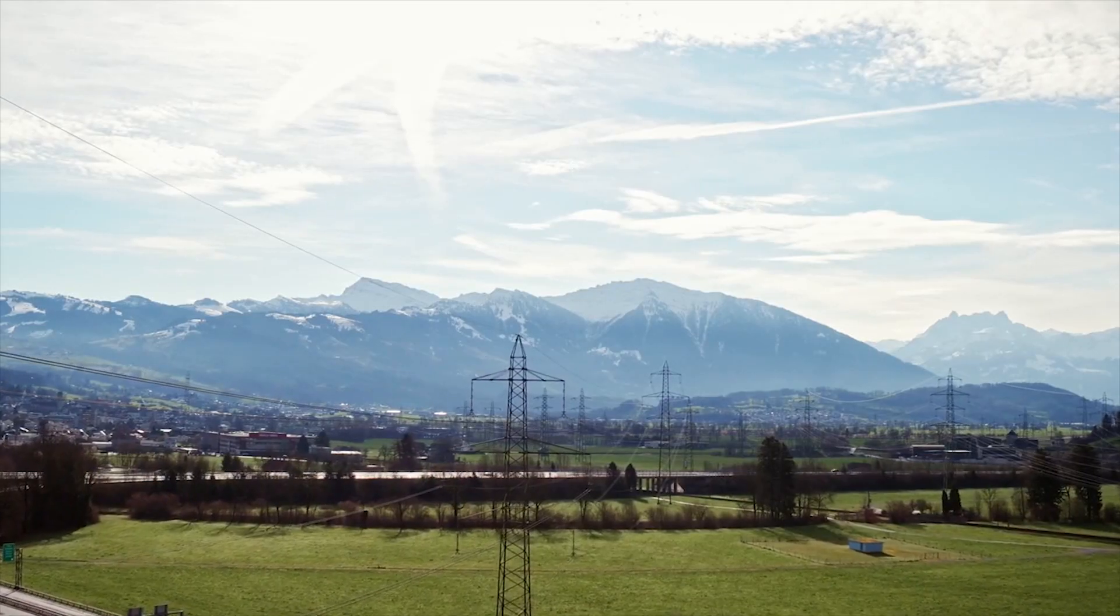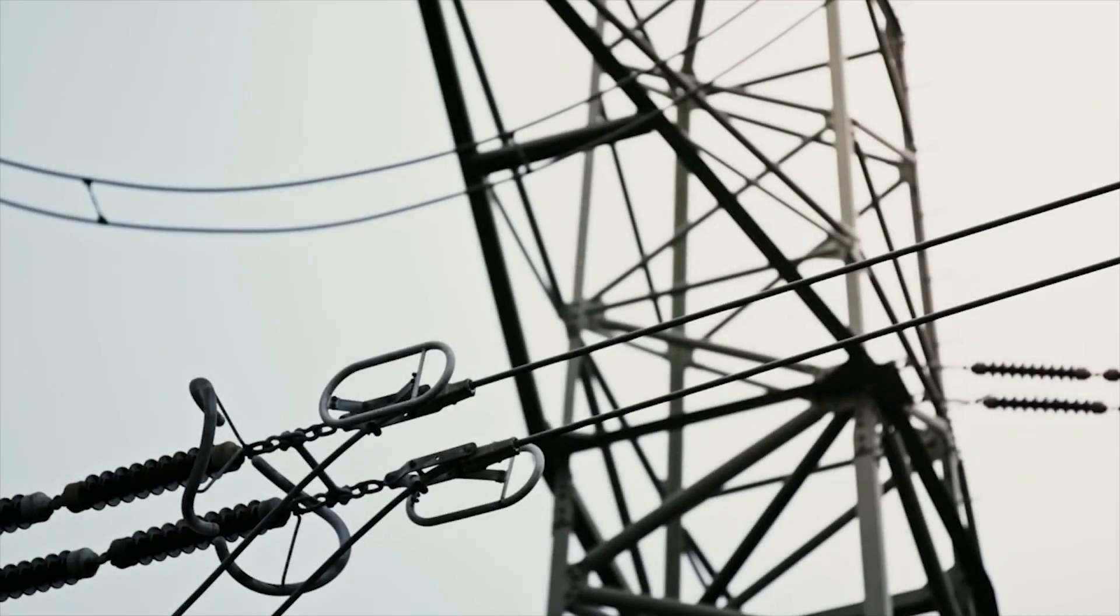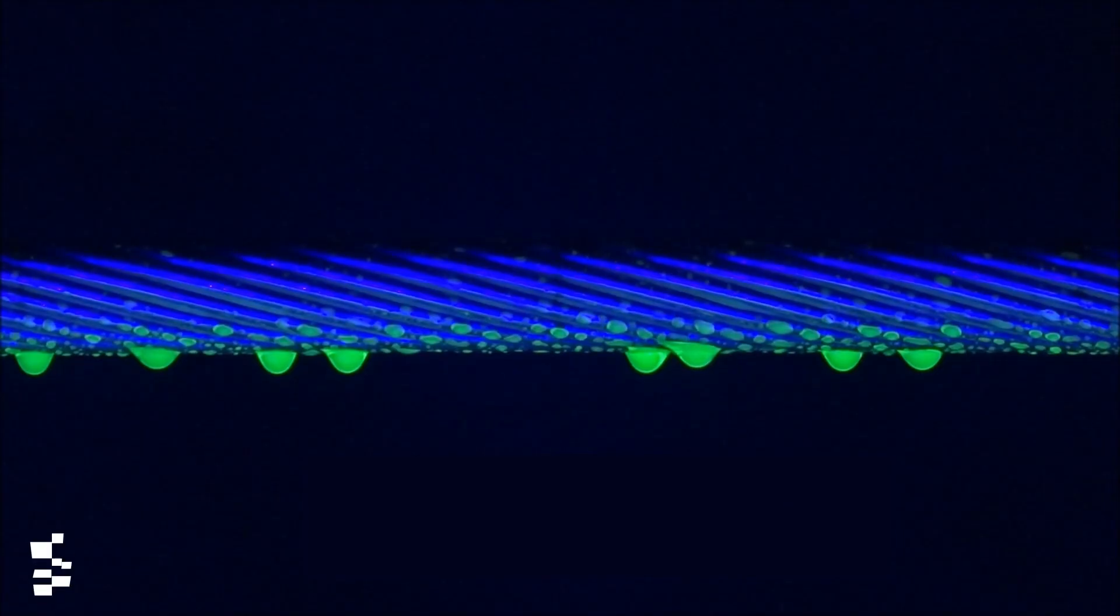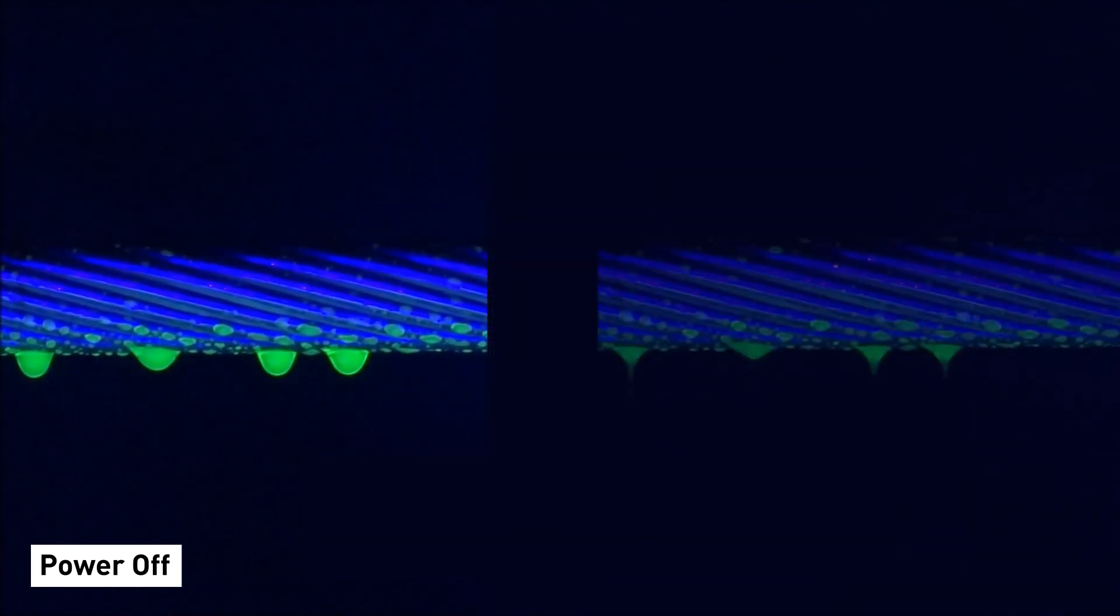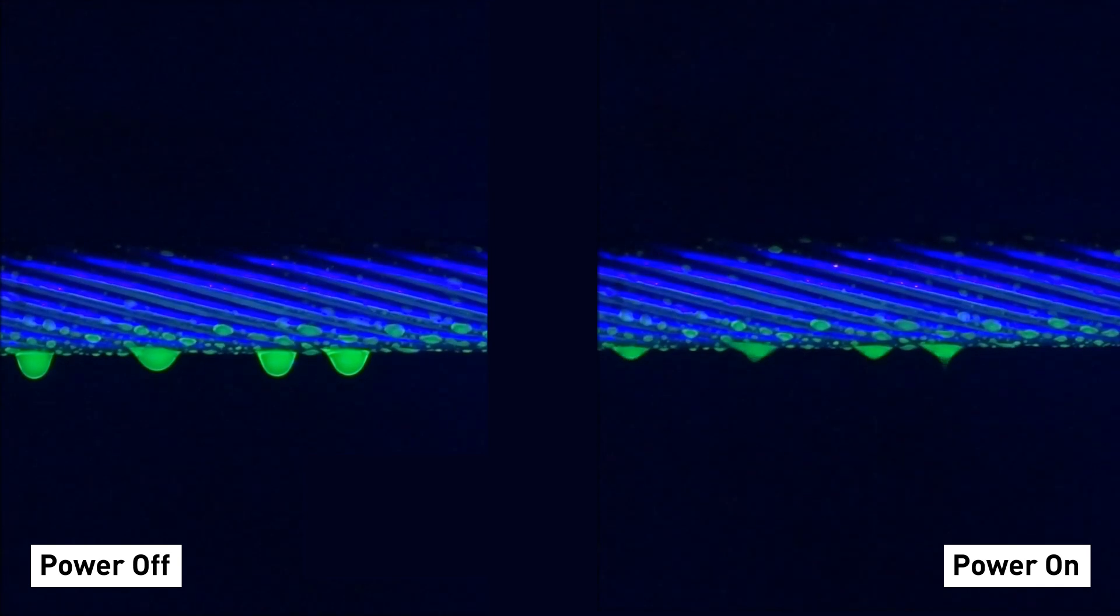In fact, every single raindrop produces a small energy loss. Corona loss originates from water drops at the conductor surface. Due to the electric field, they form tips. These themselves enhance the electric field locally and create low energy sparks.